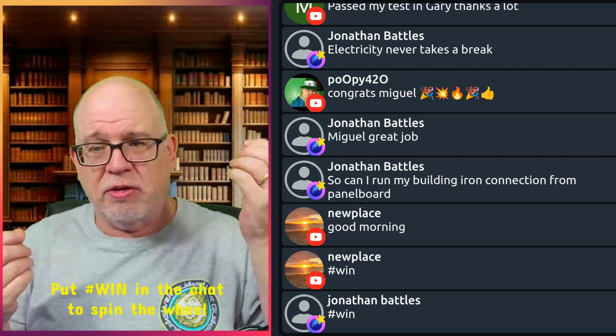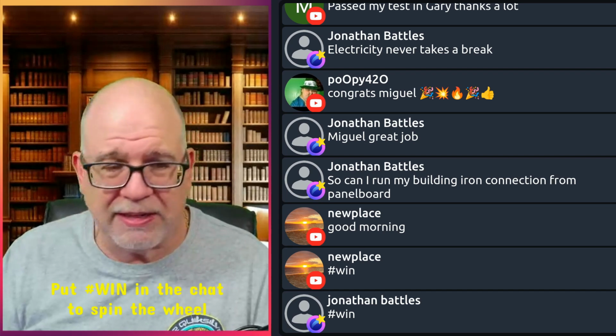And again, (E) is talking about if you happen to be doing it with ferrous raceways that are protecting that grounding electrode conductor. My recommendation: don't do it. Don't use a ferrous raceway to do that. Use Schedule 80 PVC. It's perfectly fine, and it eliminates all that other bonding crap that you have to deal with. It's just my advice to you.